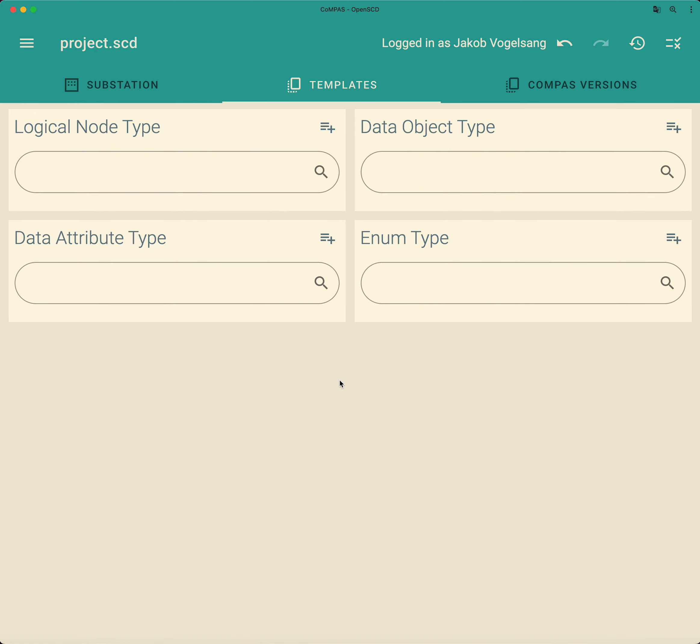Now if you want to do that, you have to know that such a logical node type PTRC must have at least one data object that is of the type behavior. And then you also must know that this data object behavior must point to a CDC class ENS. And then you must know that such a common data class CDC ENS must have at least three data attributes.